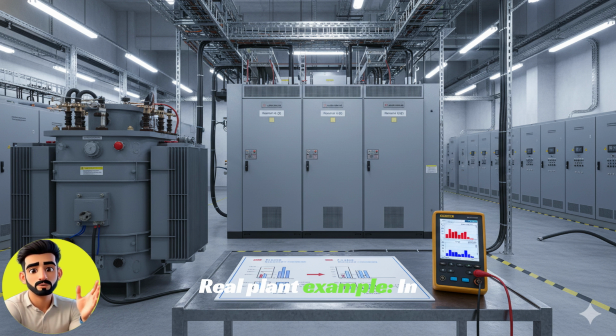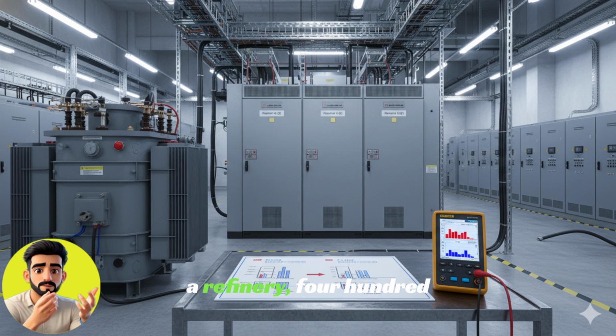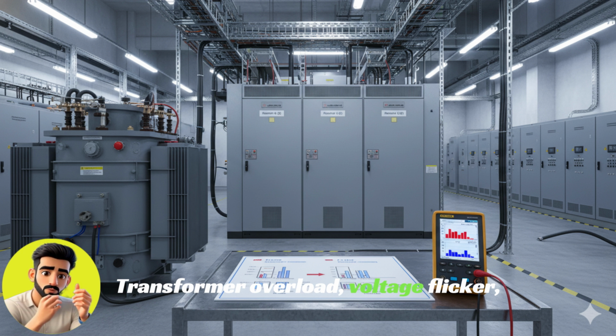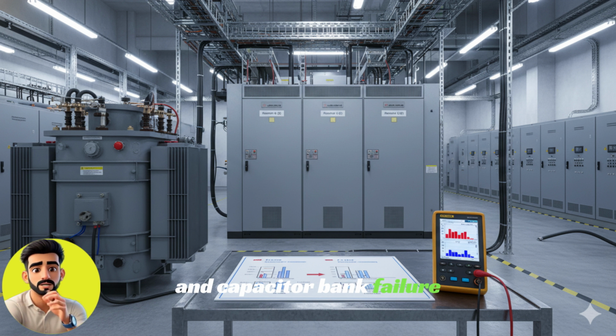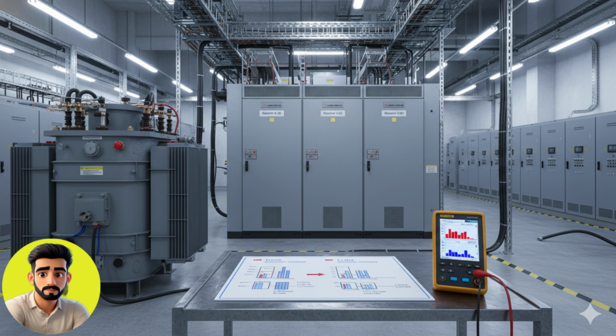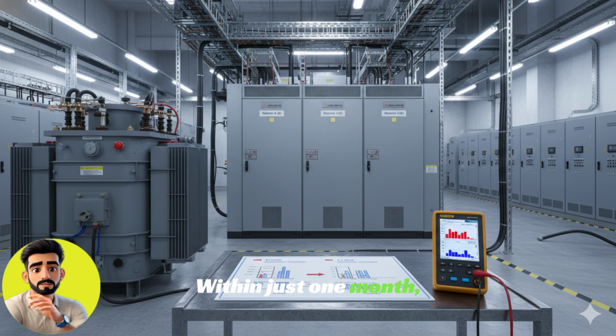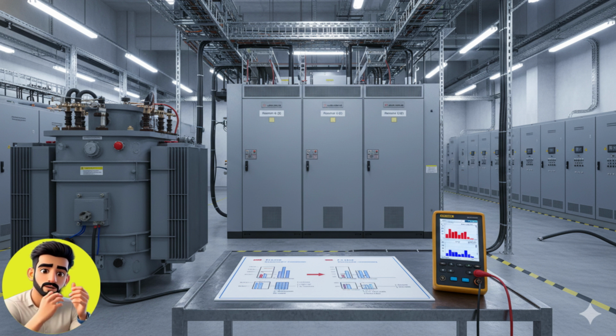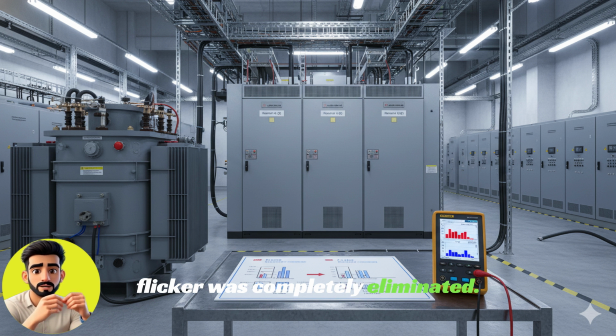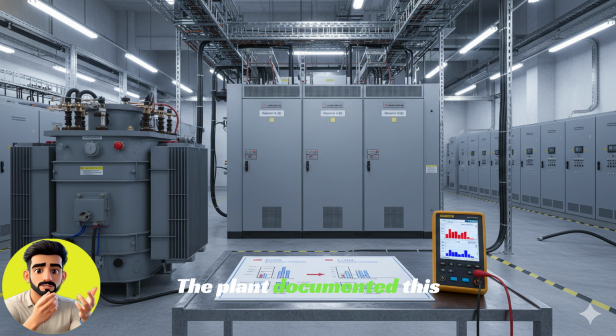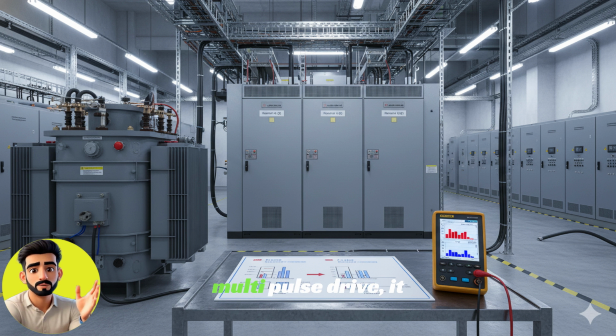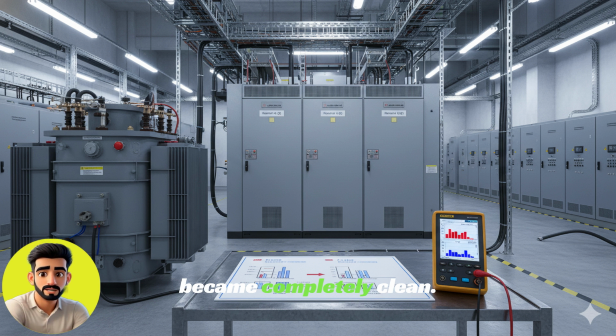Real plant example. In a refinery, 400 kilowatt VSD loads were initially 6 pulse. Transformer overload, voltage flicker, and capacitor bank failure were regular issues. A 12 pulse drive was installed. Within just 1 month, the transformer temperature reduced, power quality improved, and flicker was completely eliminated. The plant documented this in writing: after the multipulse drive, the power quality became completely clean.